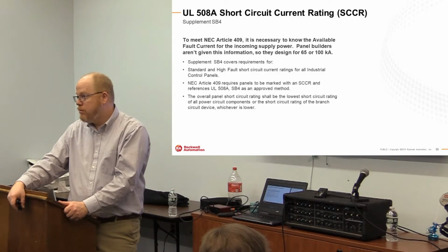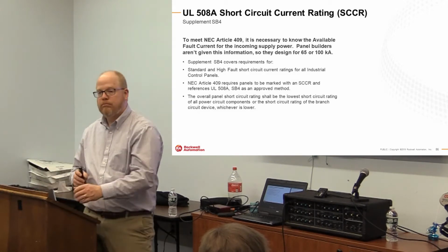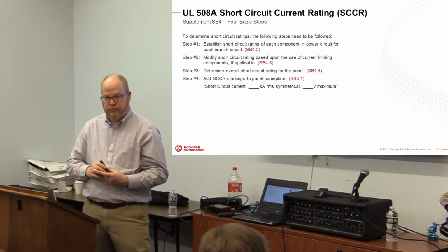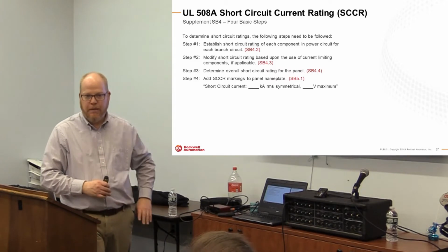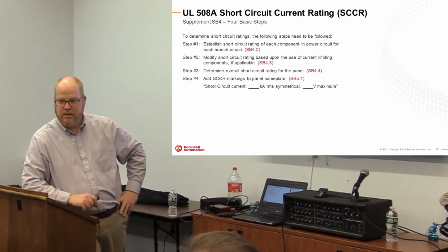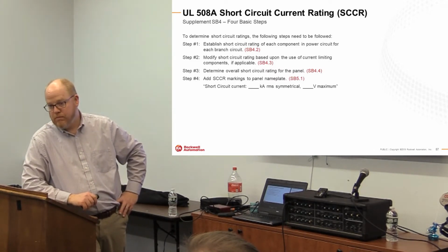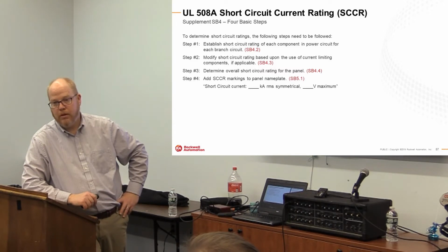Does that make sense? Your box is safe up to 65 or whatever. So they have to limit it. Right, but I thought it was up to the owner to make sure that the sticker that's on there is based on what equipment is up ahead of it. It's based on the available current of your service. So you have to limit their feeder breaker to be below the 65. The box only represents the components, ideally, but we have no way of knowing that.